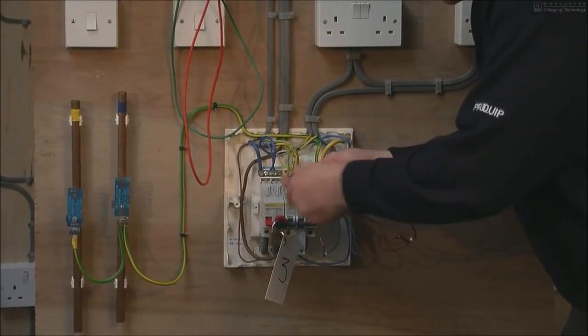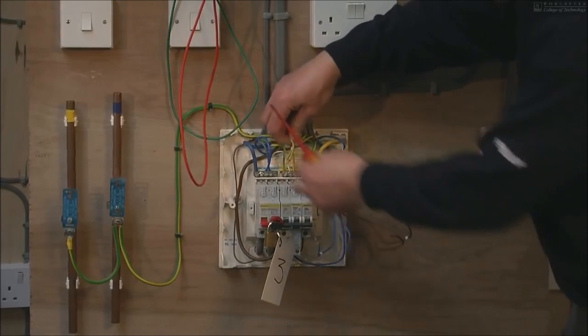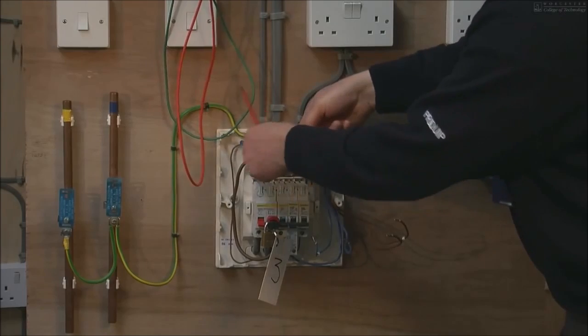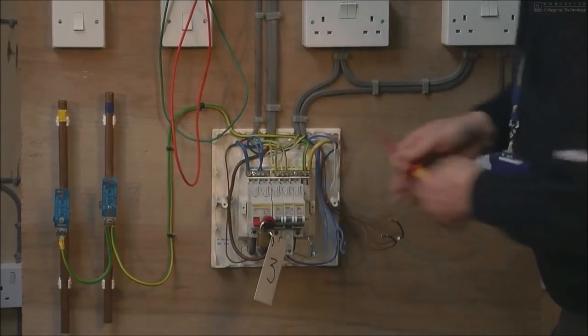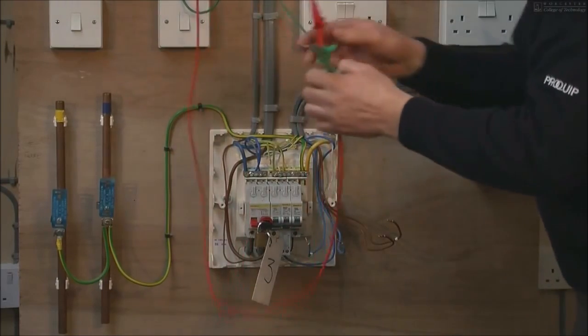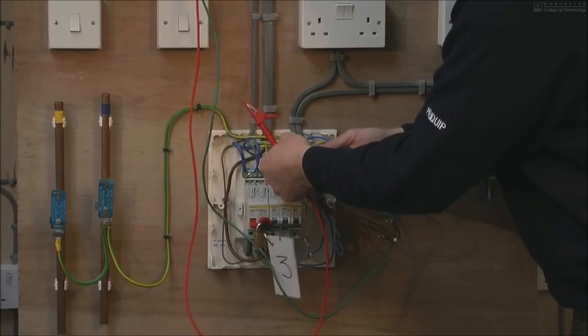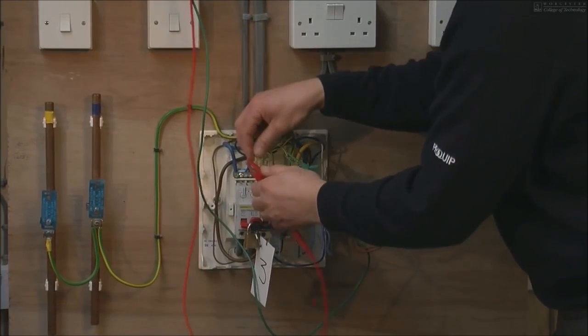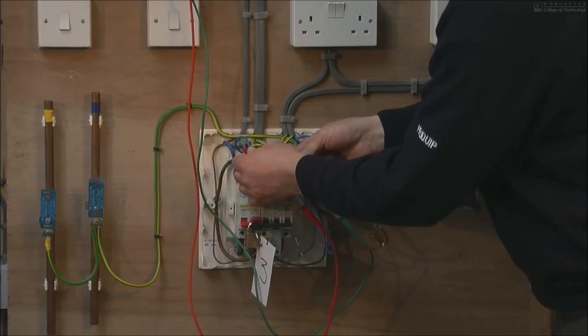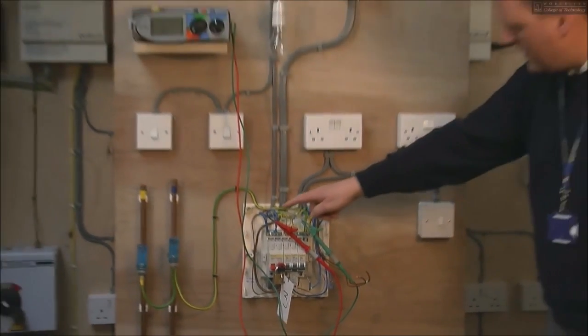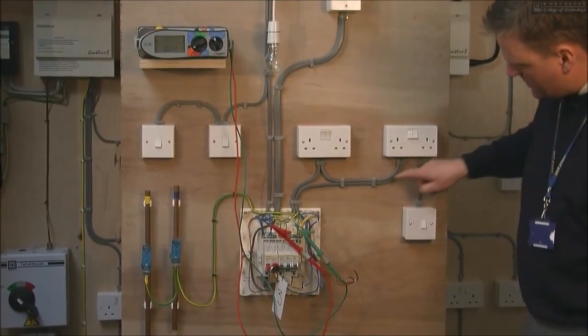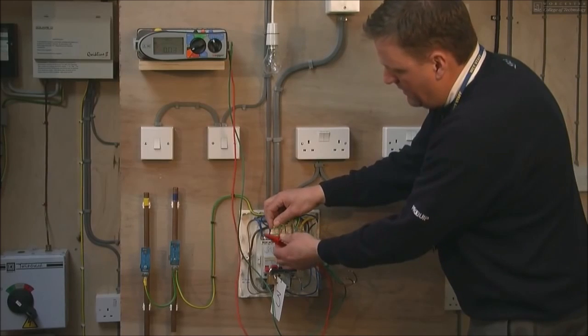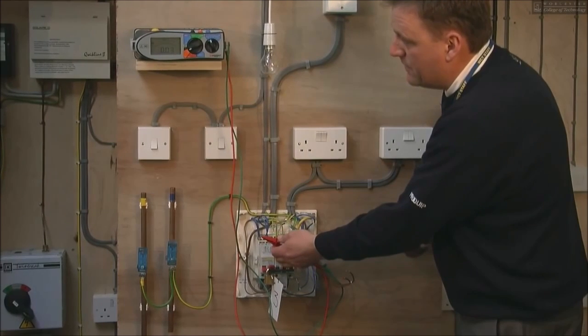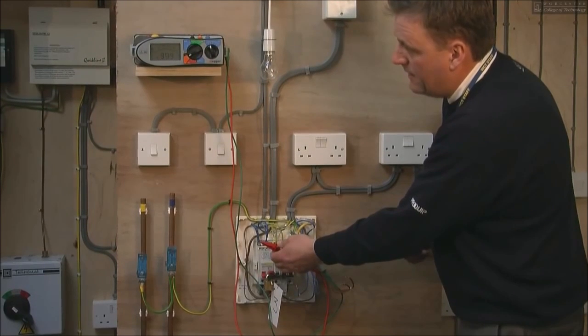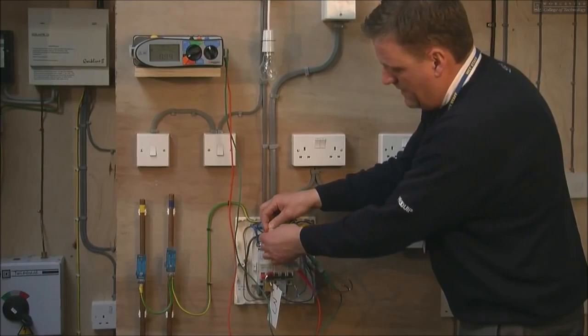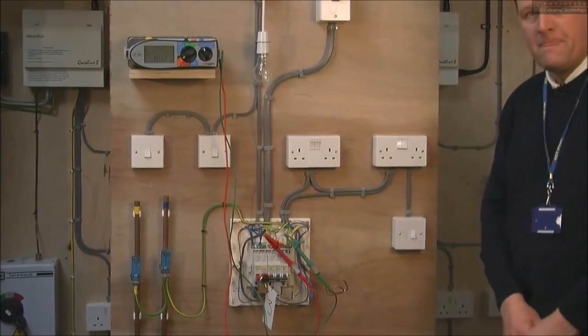We then take out the two CPC cables. And again we separate them. And again we put the test leads onto the two ends of the CPC, make sure they're pinched nice and tight. And again this is testing the continuity of the CPC through the circuit. And again, if we didn't have continuity, the meter would read an open circuit like so, as 999. And this is known as a little r2 test.